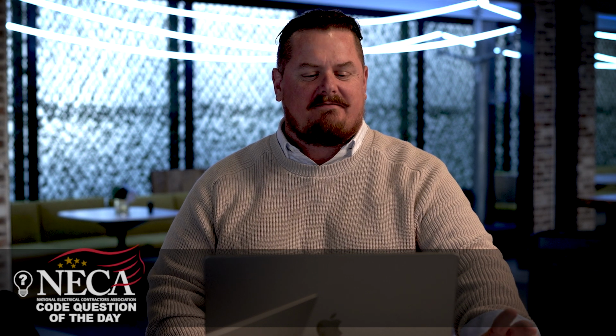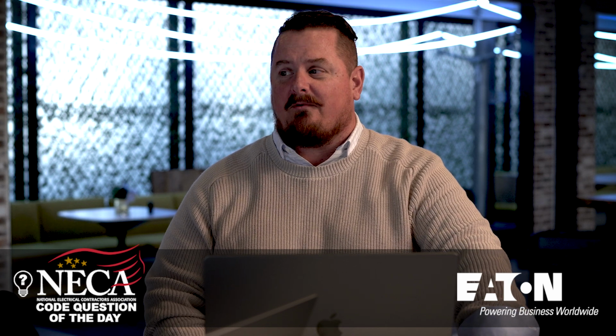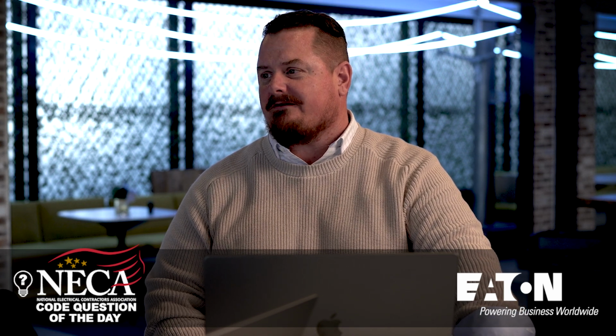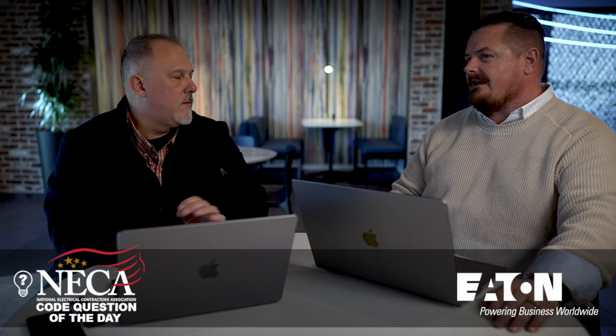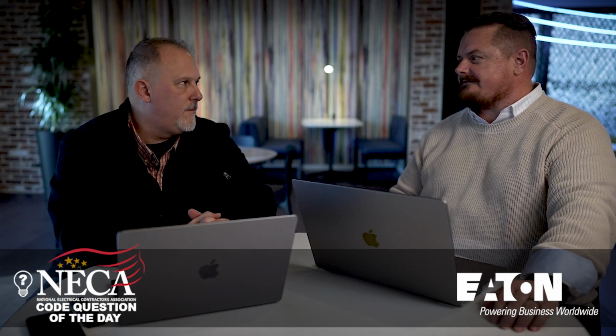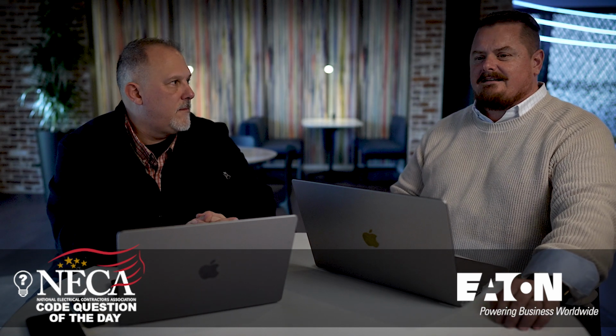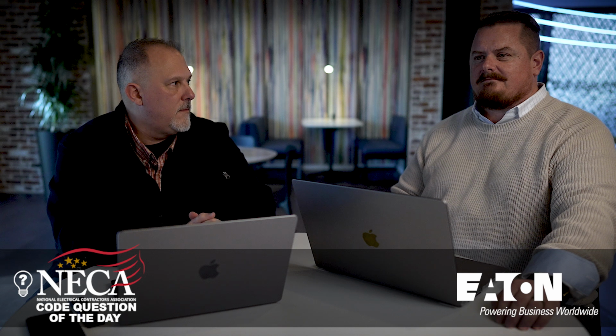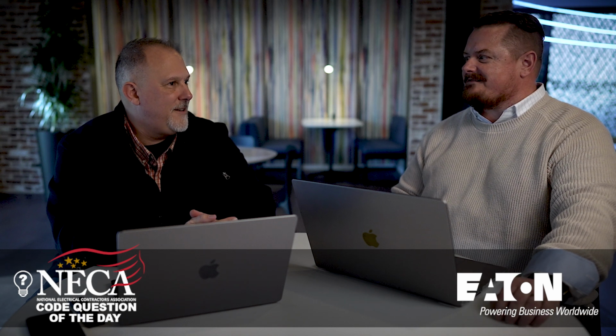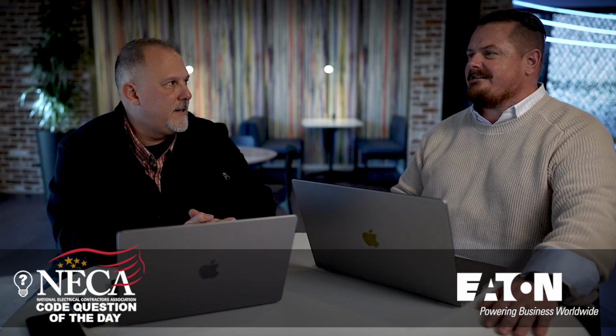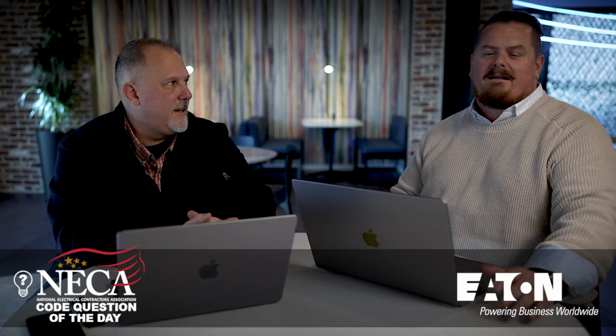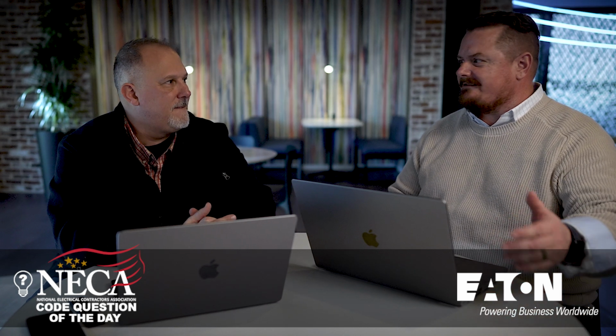So AFC, available fault current, and short circuit current ratings, specifically for HVAC equipment. This is one I will say we get at least once a month, if not more, a question on this in the CQD and from contractors in general. It's usually in some kind of frustration or panic because they've got an installation that may not have been their choice, but they've got to deal with it, right?